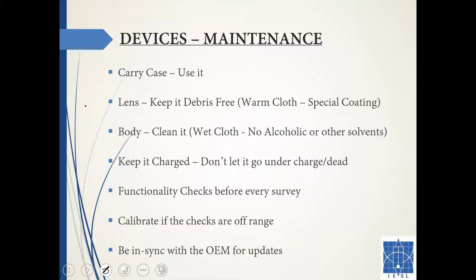Calibration and verification. This is a very interesting tip when it comes to the industry. Some of the clients ask for calibration certificates. When it comes to cameras, some say that you have to calibrate it every year, right? That is not, of course, required because your initial factory calibration is valid for at least 5 years in the field if you don't do anything stupid. But if the client insists, you can provide a verification report. Calibration and verification are two different aspects.